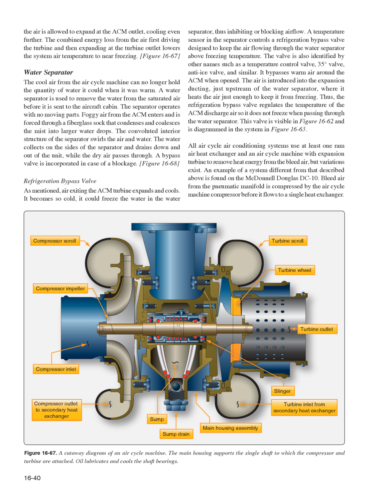It bypasses warm air around the ACM when opened. The air is introduced into the expansion ducting, just upstream of the water separator, where it heats the air just enough to keep it from freezing. Thus, the refrigeration bypass valve regulates the temperature of the ACM discharge air so it does not freeze when passing through the water separator. This valve is visible in Figure 16-62 and is diagrammed in the system in Figure 16-63.